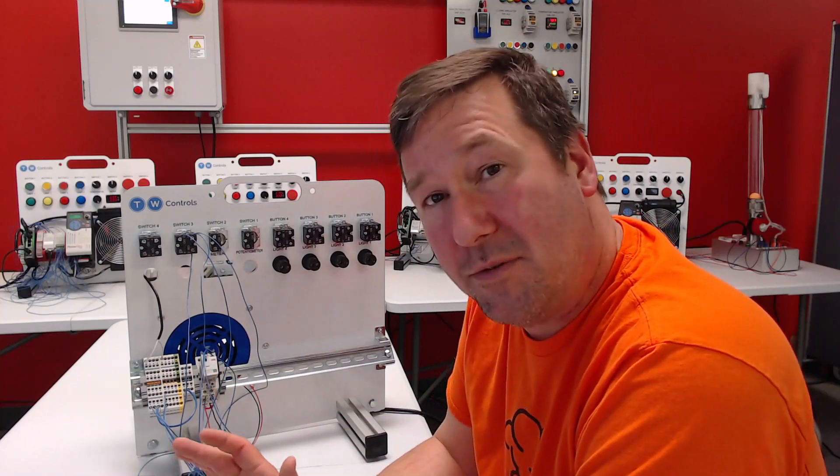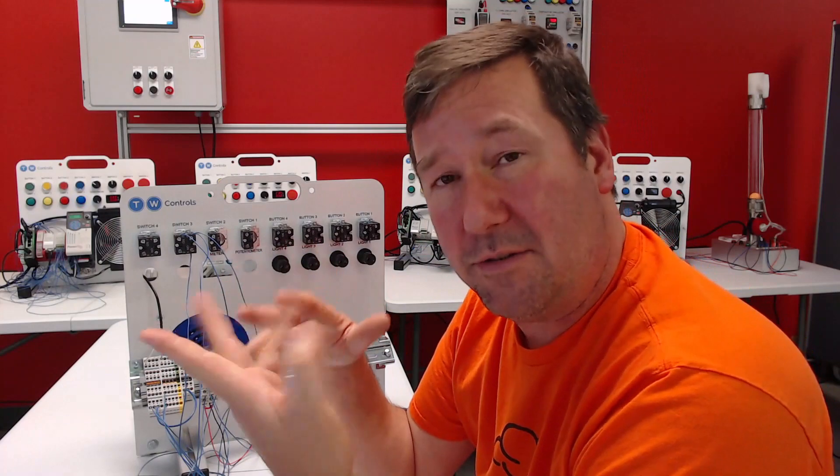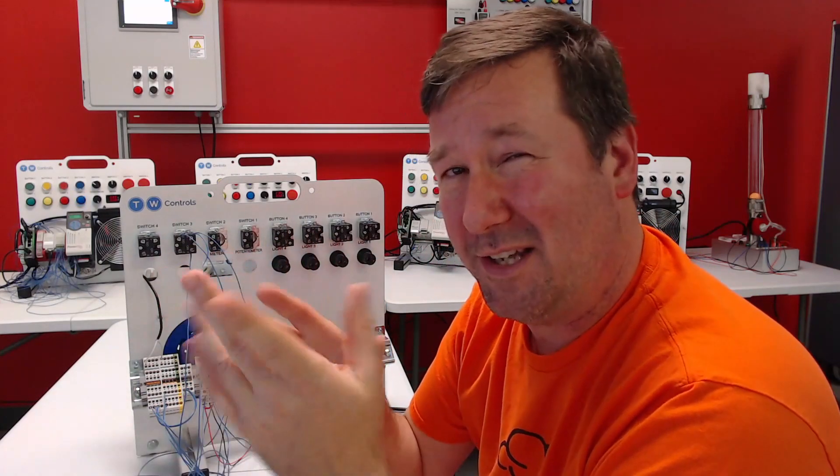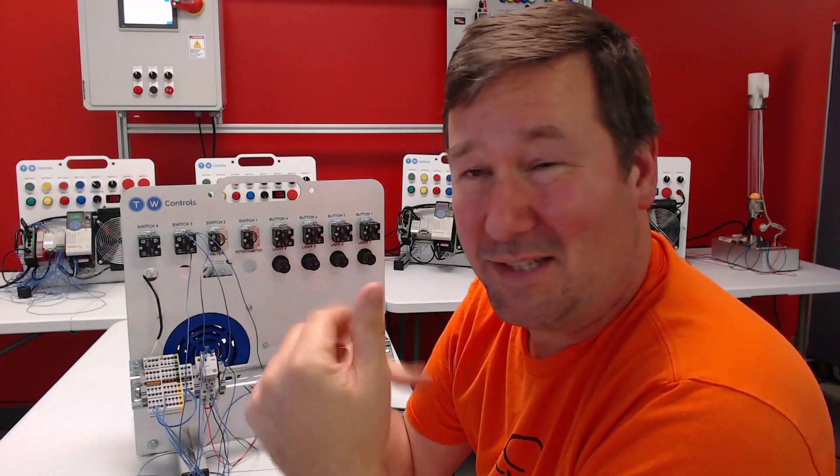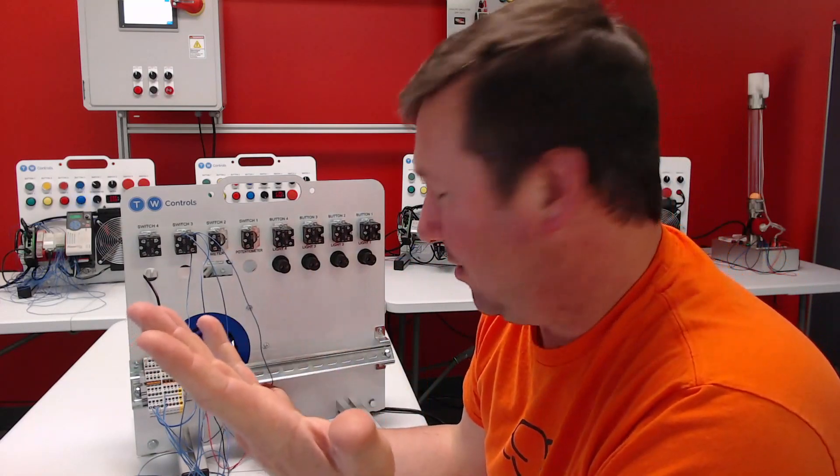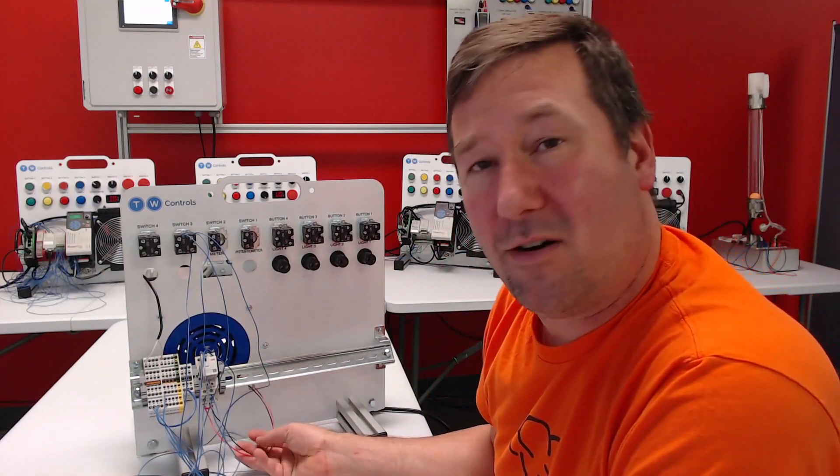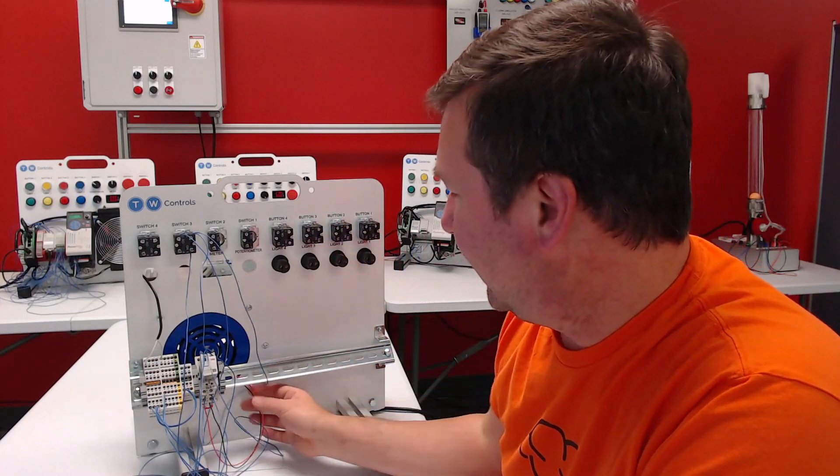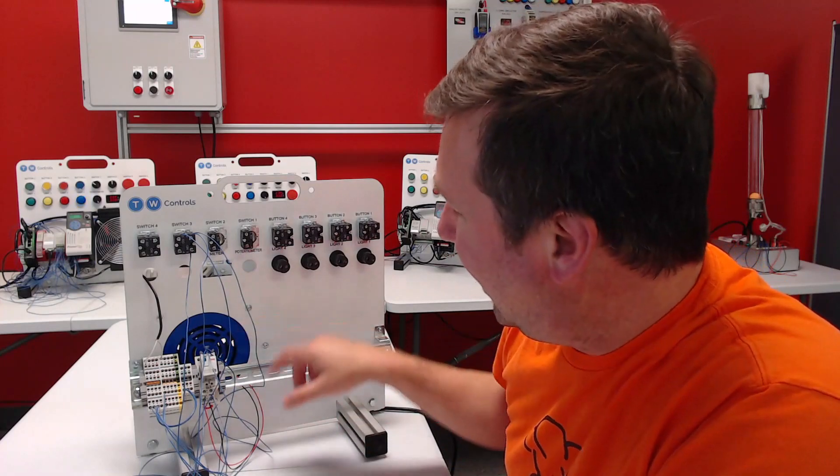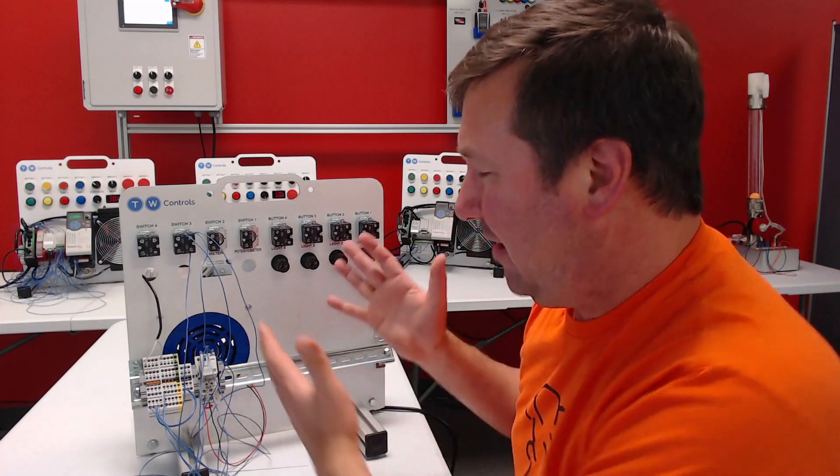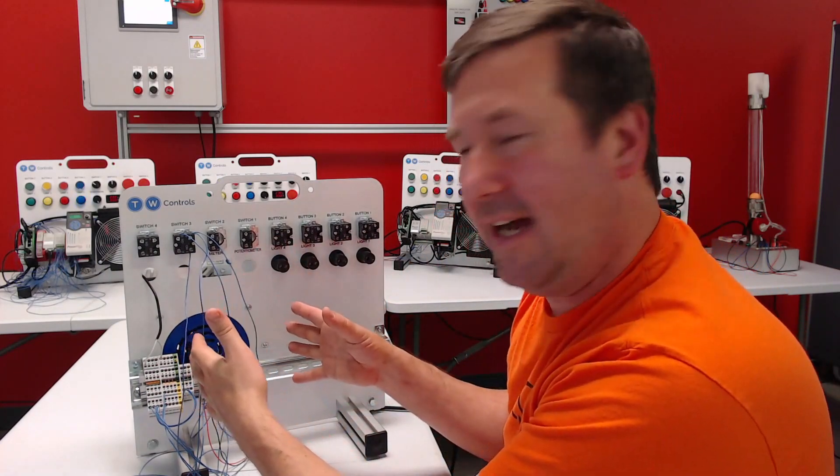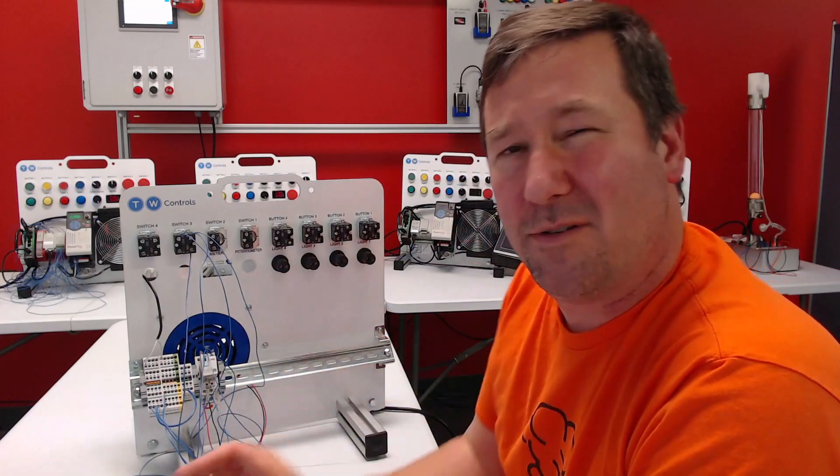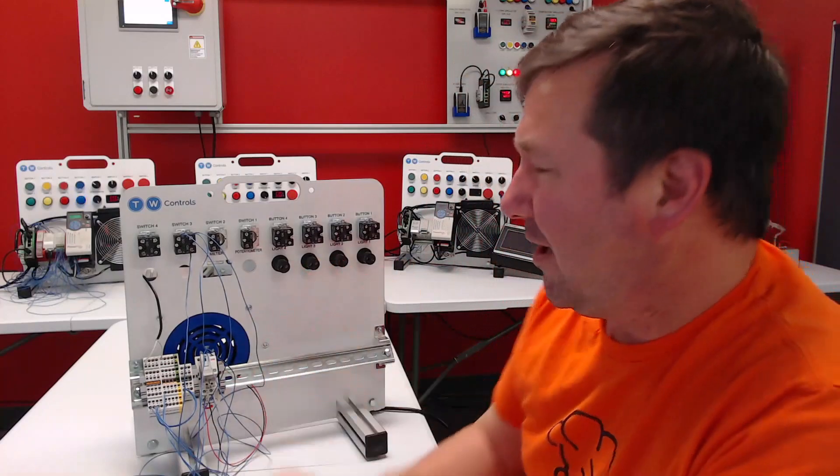Now, we do just have a single relay on this, and this is the one downfall that I clearly identify with this setup. We have a 24 volt DC motor, and a lot of people will say, 'well, you've got to switch two wires to reverse the DC motor.' Well, no, that's not true on your typical fan motor, or I'll say your typical DC motor that you're going to run into outside of ones that are clearly reversible. These are set up with usually some type of pulse width modulation thing in it, not really sure the exact details, and it is only designed to run one direction. So I don't have the option on this trainer to make like a reversing contactor design and be able to reverse the motor. That's the only thing I really see that it's like, 'yeah,' but we can do a lot of wiring exercises.